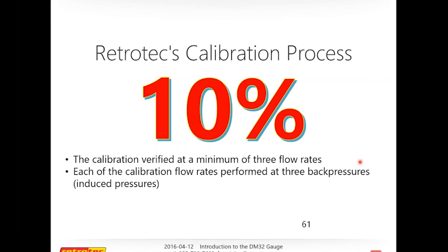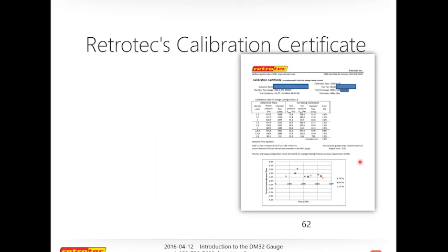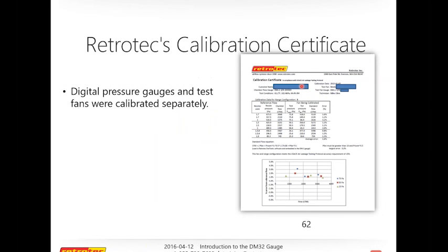So the point being that each one of these pressure points gets multiple tests, and when you get your gauge, you will get a calibration certificate. And I have redacted some of the important information here because this is an actual calibration certificate. So it just says that all pressure gauges and test fans are calibrated separately, not all at the same time, each one individually, and it must be verified every 4 years. So we've changed that now to 5 years, so I'm sorry, I'll take that back.